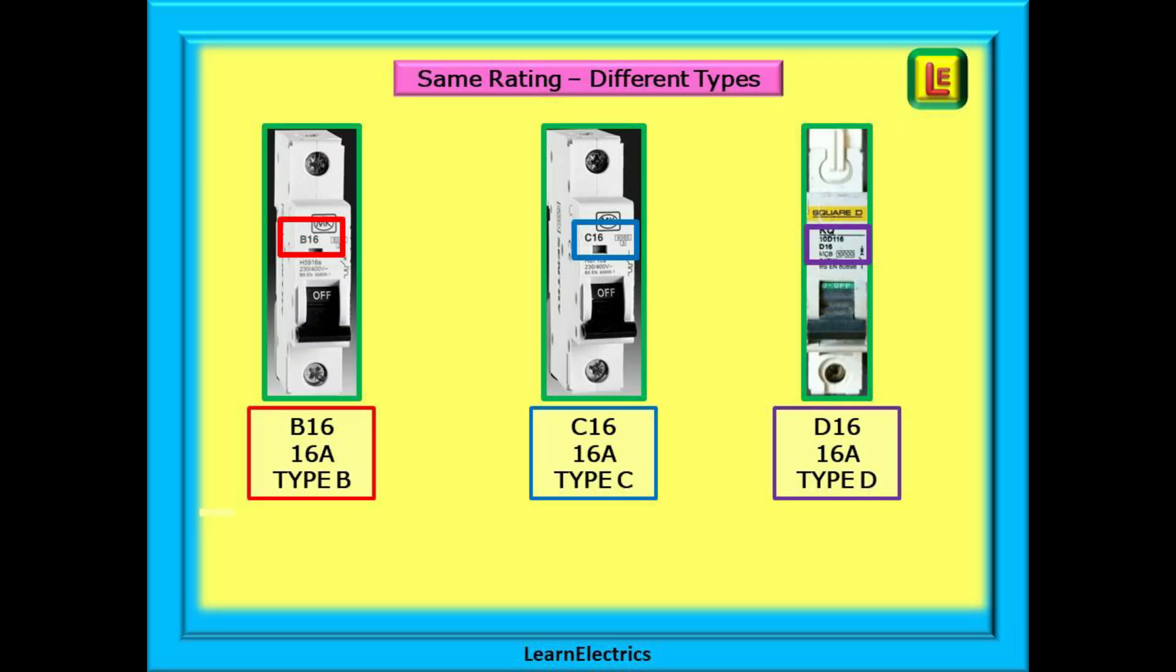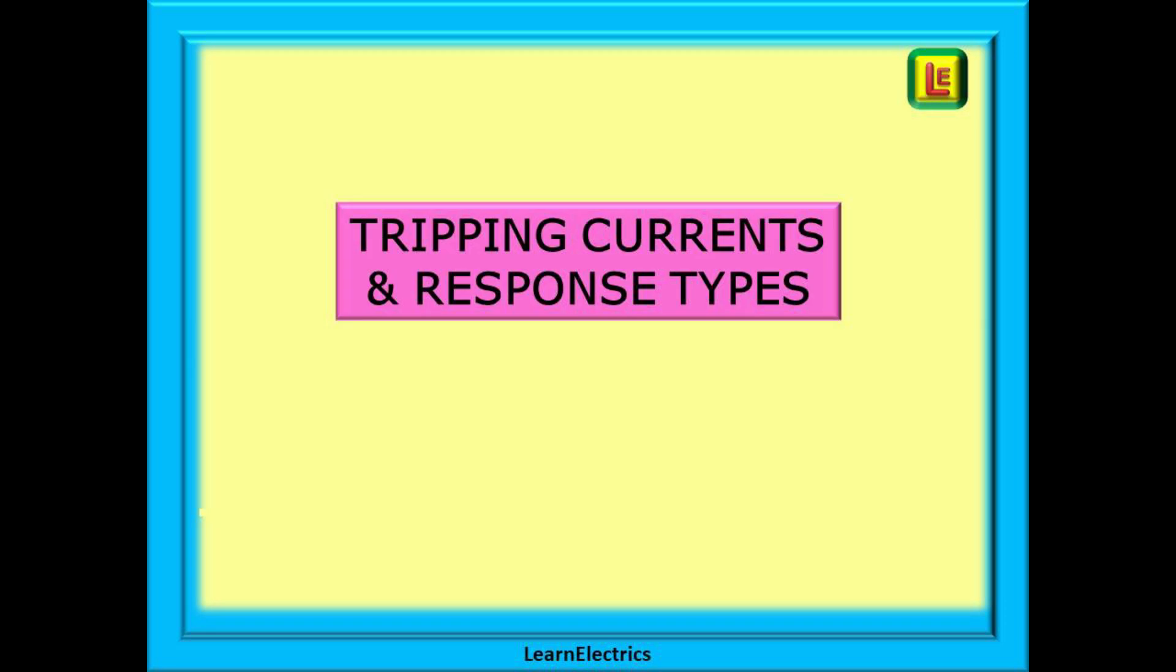We can have the same amp rating of MCB with different type numbers or letters. A B16 device has a 16 amp current rating and a type B response curve. A C16 device has the same 16 amp current rating but a type C response curve. And a D16 device will still have a 16 amp current rating but with a D type response curve. So let's have a look at the tripping current and how this works with the response curves.